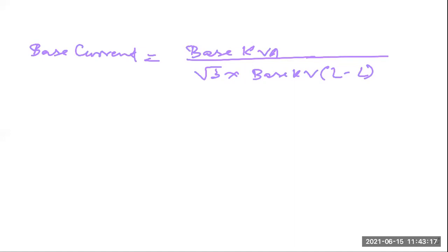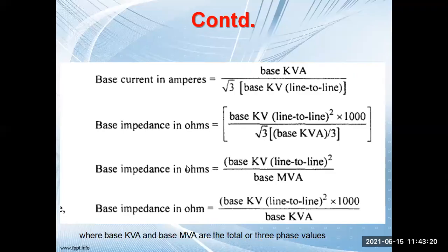Next is base impedance in ohms. How do we calculate the base impedance? It is base kV squared divided by √3 into base kVA by 3 into 1000. How do we arrive at this?